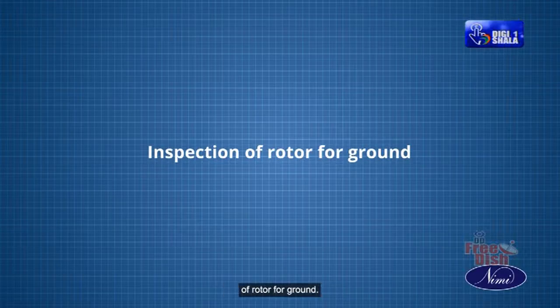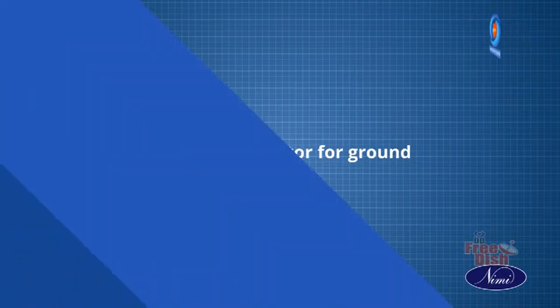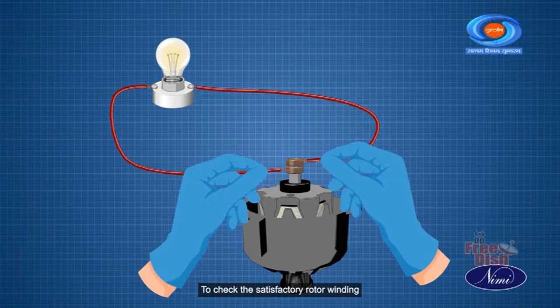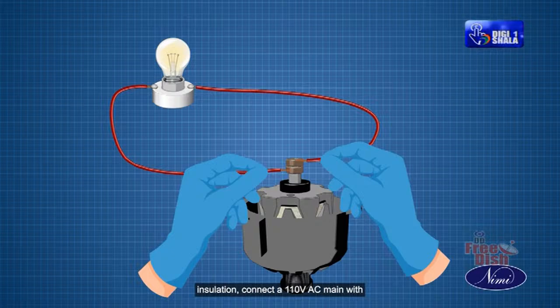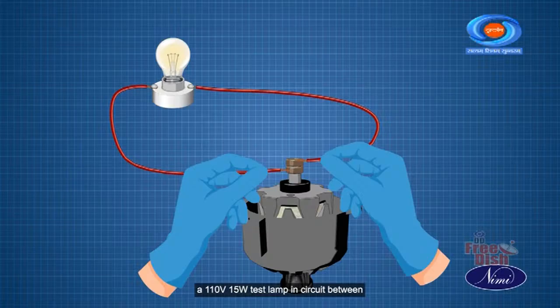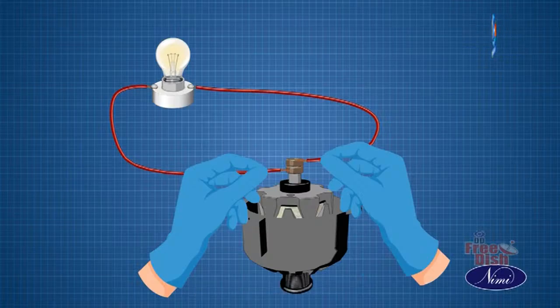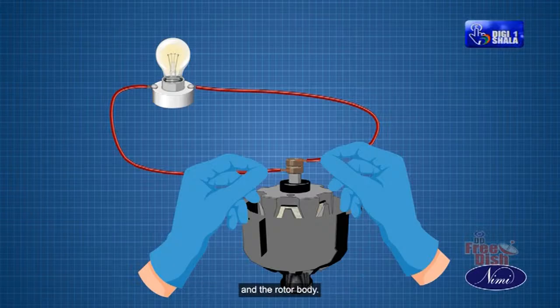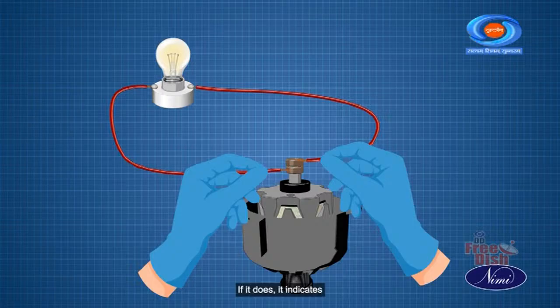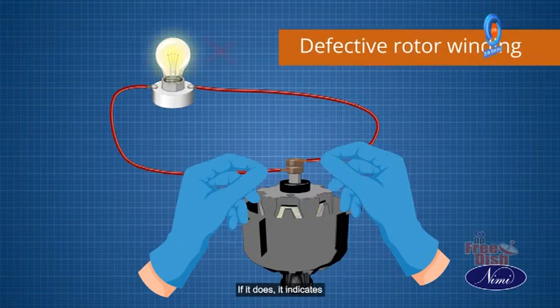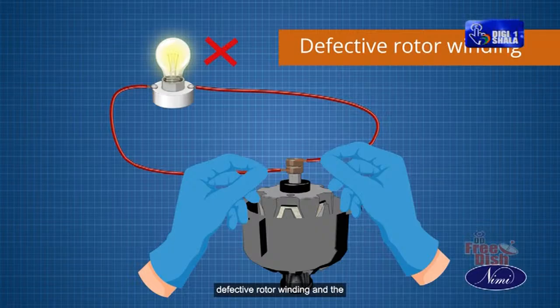Let us discuss the inspection of rotor for ground. To check the satisfactory rotor winding insulation, connect a 110 volt AC main with a 110 volt 15 watt test lamp in circuit between either of the slip rings and the rotor body. The lamp should not glow. If it does, it indicates defective rotor winding and the rotor assembly needs renewal.